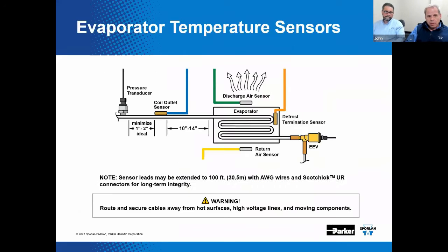That's correct. Now here we're showing some of the sensors that are needed to make all this work. The S3C control system uses input from several sensors to control case, discharge air, superheat, and defrost. It's important to follow these suggestions, or instructions, to ensure proper location and mounting technique. All sensors should be provided by us, right? By us, Sporlan. Absolutely. If you want to make sure that they work and that they're compatible and that they operate as expected. We've got a torque requirement here of 3 to 5 inch pounds.